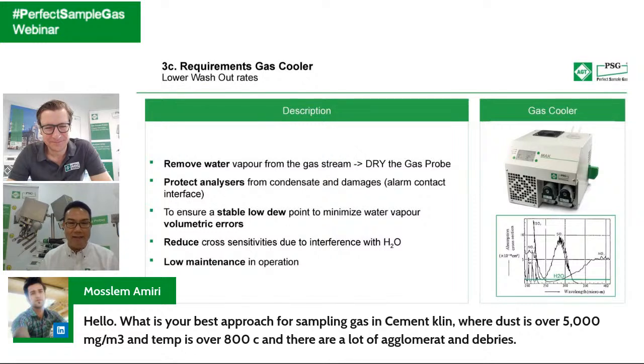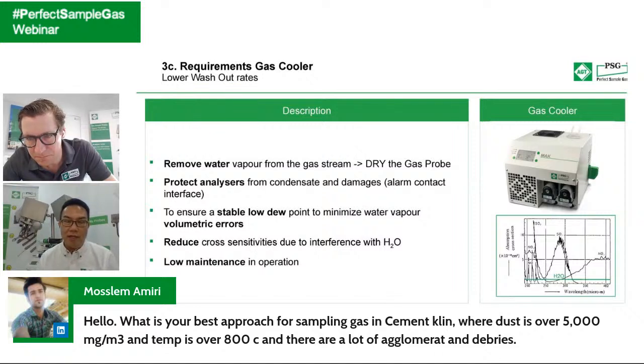We have done many sampling systems on the analyzer side, right? We do not offer a complete rotating kiln solution. We do not have a scavenger probe. We do not have an oil cooling or water cooling system, and we do not have the PLC control. What we have is only the analyzer sampling system of the rotating kiln. So what we have been doing all this while is that we are the third party who provides and supports solutions to a rotating kiln supplier. All right. So the answer is that we do not provide a complete solution, but only on the analyzer side.